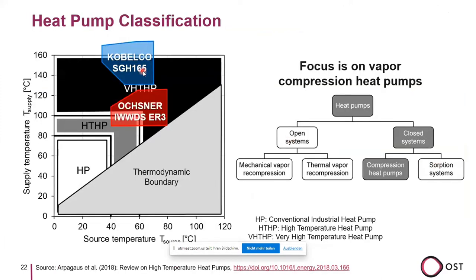When we put these two heat pump operating maps from Kobelco and Ochsner into this heat pump classification diagram, we see that they are located in what is called the very high temperature heat pump area. We focus, as I said, on vapor compression heat pumps, which are closed systems, or also open systems with mechanical vapor recompression. In this presentation I do not cover this field.